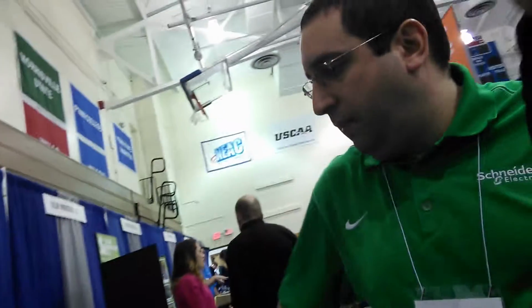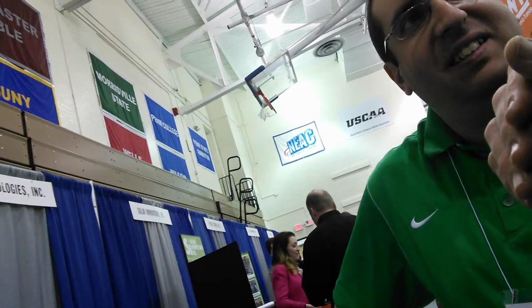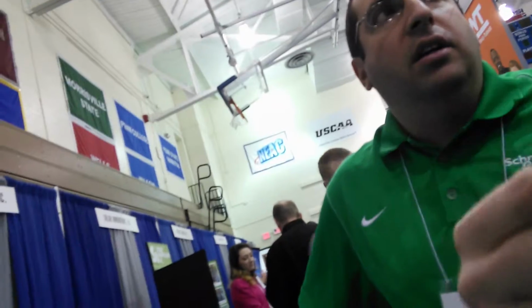Now, as far as diagnostics, we had a classroom that I was teaching in that had a noise that came on every 2 minutes. After 2 or 3 weeks, finally, it was determined it was a bad blower. Would your other system tell you that there's a bad blower if you turned on the blower but it actually didn't start? Yes. So if Penn College had that system, they could probably go to my classroom and figure out which blower. But they actually had to physically go up and listen for it.